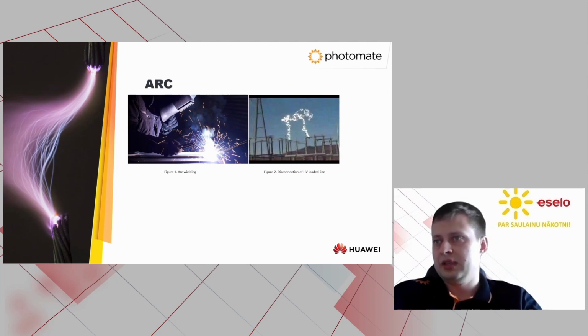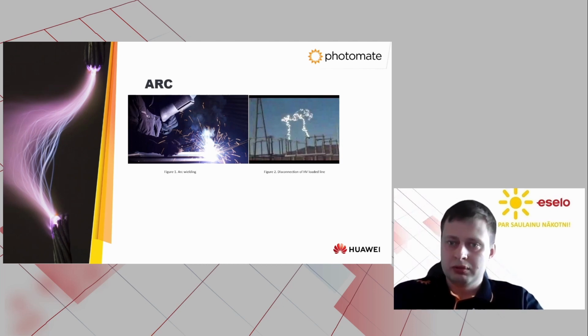So as you see in figure 1, an arc welding machine is shown. The principle of the arc flash is pretty much the same. Several factors can cause arc flash in a photovoltaic system, including loose wire connections, bad crimping tools, or damaged insulation of the wire.